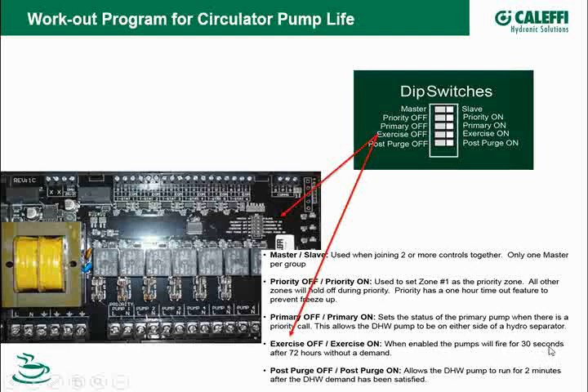So during the downtime, during the summer, something like that, the pumps get moved a little bit so they don't have a tendency to seize. Some of these new pumps are only about 30, 40-watt pumps, so they don't have a lot of starting torque. If there's any dirt and debris, or if you've got bad fluid quality, you want to make sure that you spin that pump every now and then, keep it free, keep it moving so it doesn't seize up. If you're installing these types of controls on your system, look for one that's got these different functions on it, like an exercise program, post-purge, and some other things too.